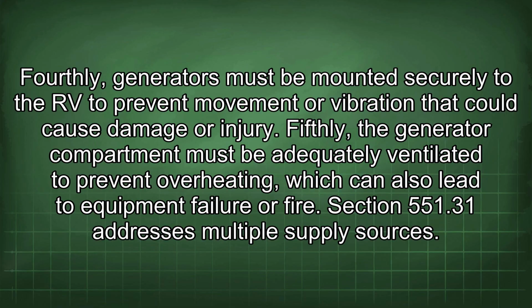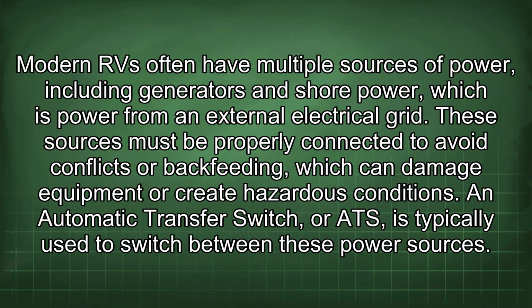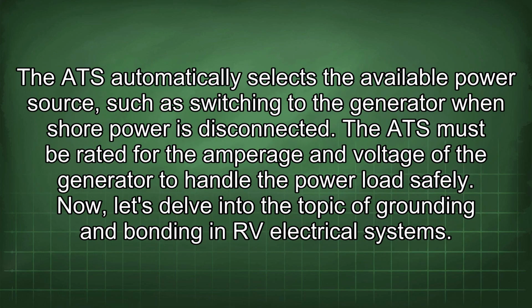Section 551.31 addresses multiple supply sources. Modern RVs often have multiple sources of power, including generators and shore power, which is power from an external electrical grid. These sources must be properly connected to avoid conflicts or backfeeding, which can damage equipment or create hazardous conditions. An automatic transfer switch, or ATS, is typically used to switch between these power sources. The ATS automatically selects the available power source, such as switching to the generator when shore power is disconnected. The ATS must be rated for the amperage and voltage of the generator to handle the power loads safely.